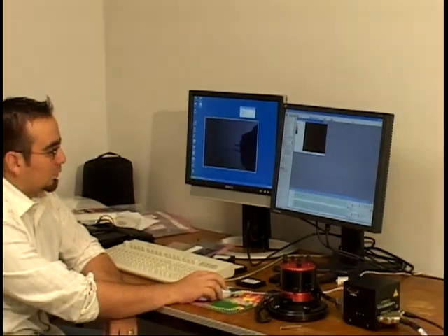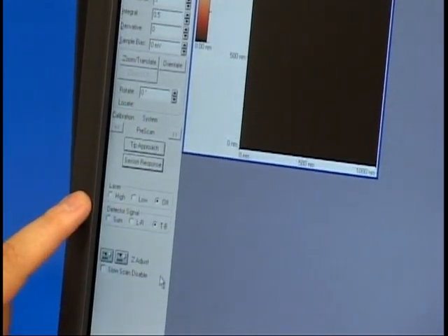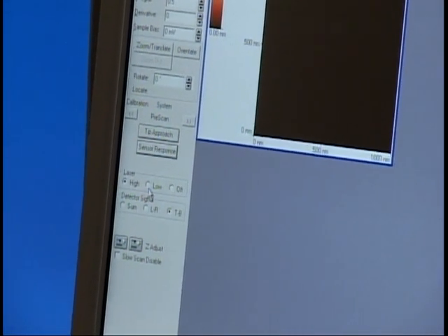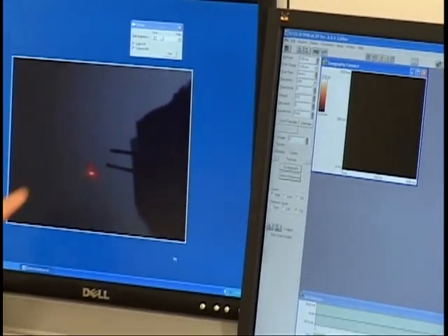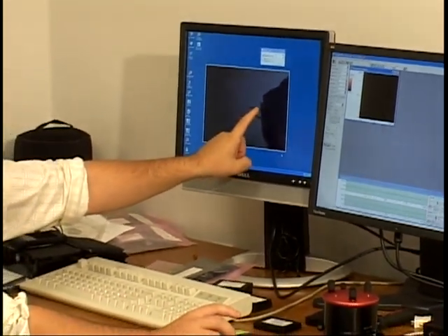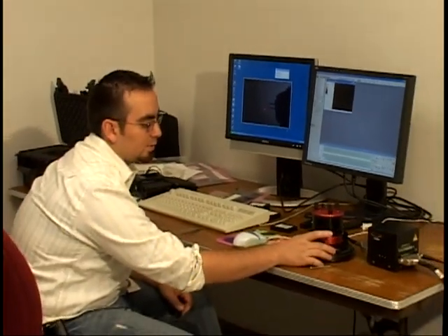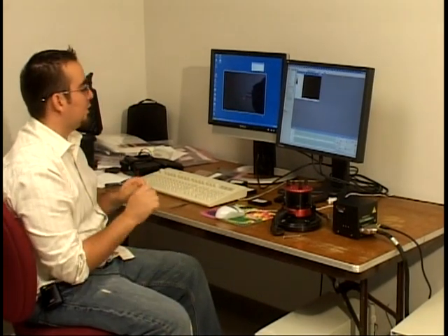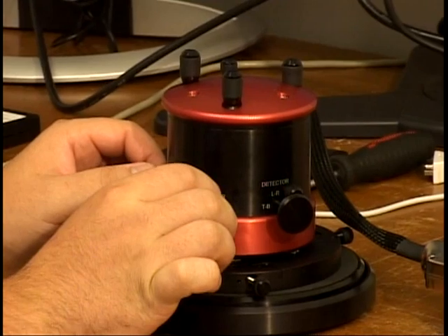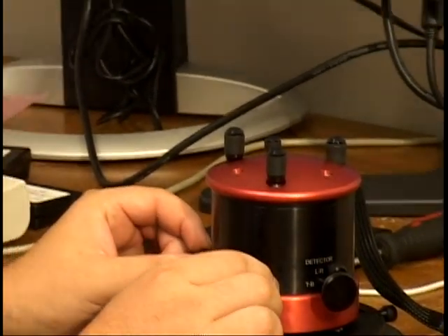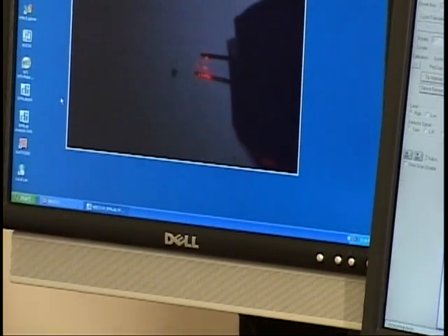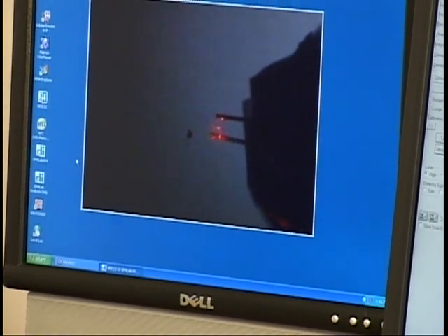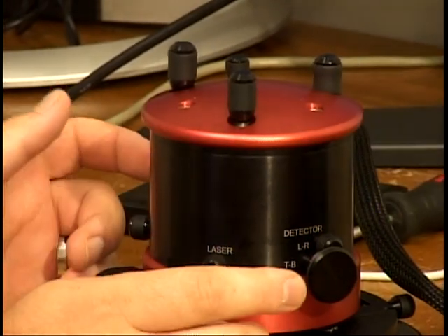Go back into the software. Down where it says laser, go to the laser window right here and click on high. Never click on low. Low has no function. So now we can see the laser on the video screen, and here's the probe still. You can still distinguish the probe right here. So we want to use the two laser knobs on the head to move the laser onto the probe. This is more of a skill you'll have to pick up, how to walk the laser onto the probe. Once you get the laser on the probe, pull out both knobs. It's like disengaging the screws.